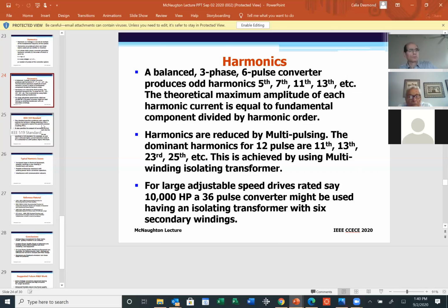Now, one technique that is widely used in the industry to reduce the harmonic impact on your other running equipment is to use what we call multi-winding transformers. The higher the number of secondary windings, the more harmonic cancellation. Typically, I'm giving an example here: a large adjustable speed drive, 10,000 horsepower. It is a 36-pulse converter that will use an isolating transformer with six secondaries. This way you're able to address or suppress the harmonics with respect to the primary side. But with respect to the secondary side, these harmonics still exist in the transformer winding.